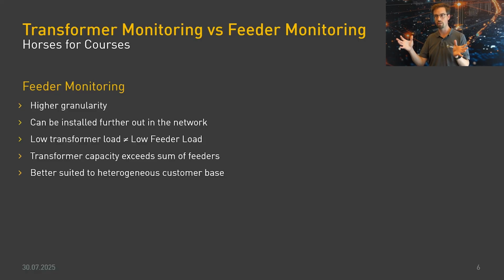If you look across your network, changes won't happen evenly across all feeders. That's where feeder level monitoring comes into its own: you can monitor the parts of your network with the most dynamic change or the highest load growth. Those are the areas where feeder level monitoring makes the most sense.